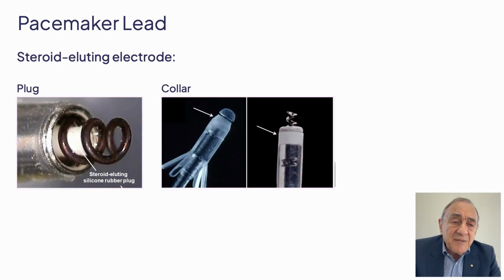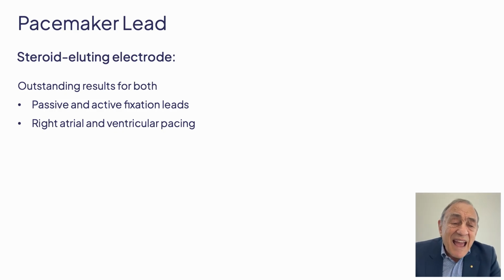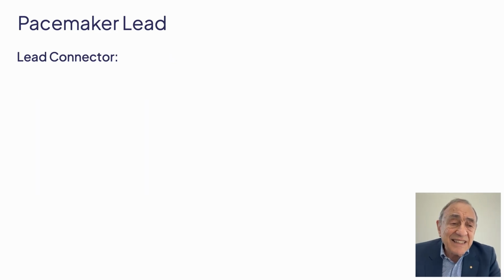So steroid has been incorporated into plugs, and to the right you can see into collars, this design being created by Telectronics in Australia. You can see also that the active fixation lead on the right can have a plug or a collar, and the result is that we have outstanding threshold levels for both passive and active fixation leads in the right atrium and in the right ventricle. Let us now look at the lead connector.